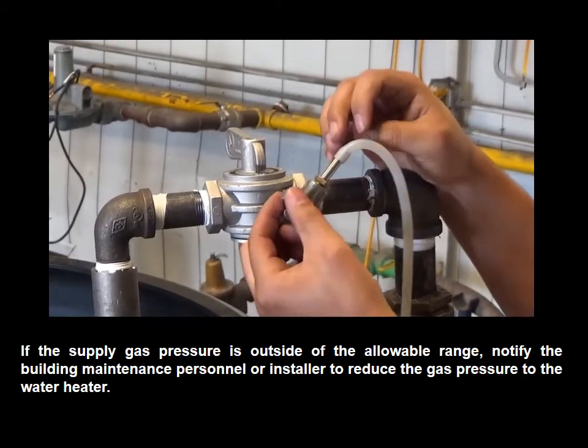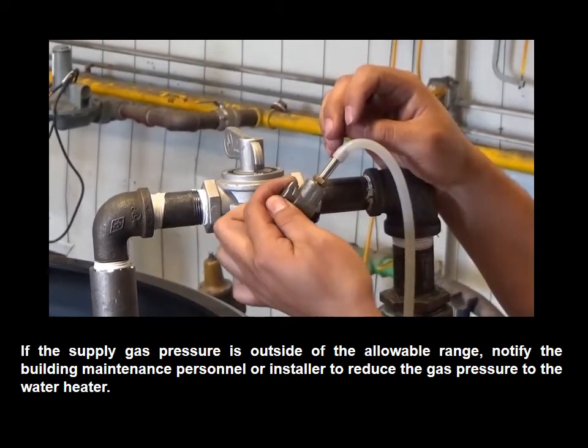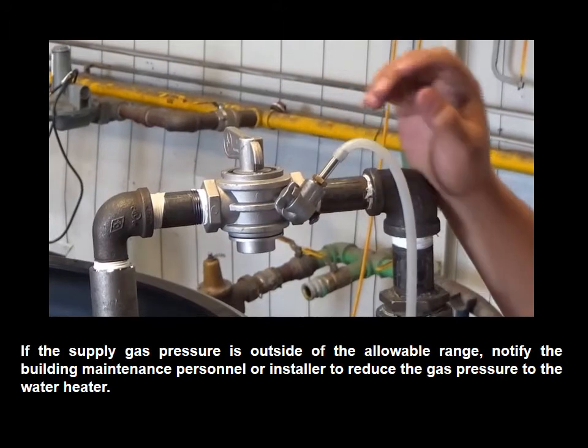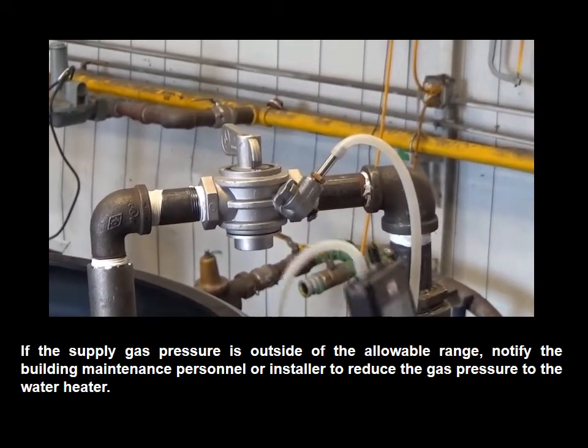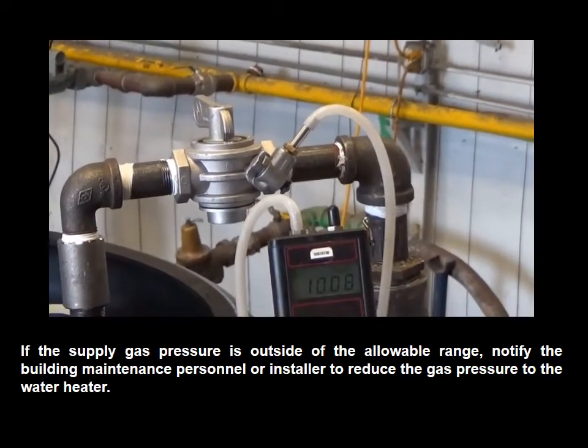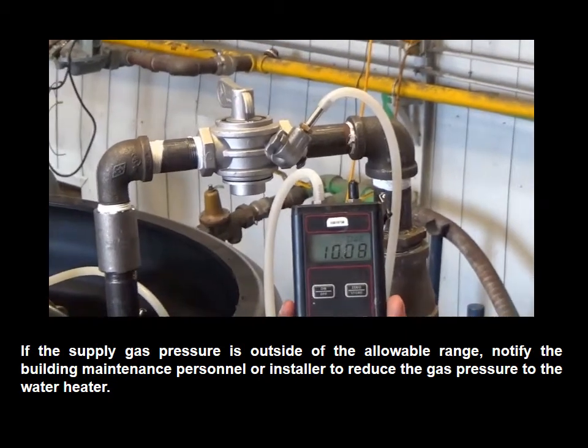Open the 1/8 inch pilot shutoff test valve and measure the gas pressure. If the supply gas pressure is outside of the allowable range, notify the building maintenance personnel or installer to reduce the gas pressure to the water heater.